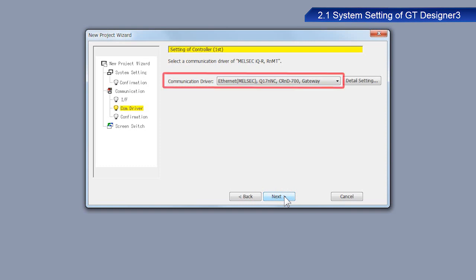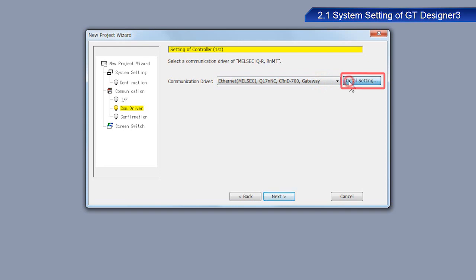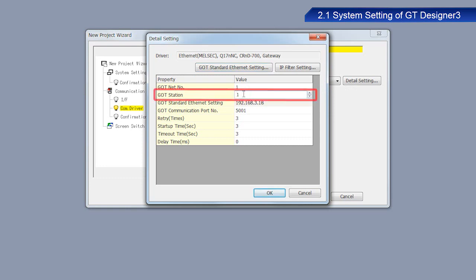Click Next. Make sure that Ethernet MELSEC Q17nNC, CRnD-700, Gateway is selected as the communication driver. Click Detail Setting. Once the Detail Setting pop-up screen appears, change the GOT station to 2 and then click OK.